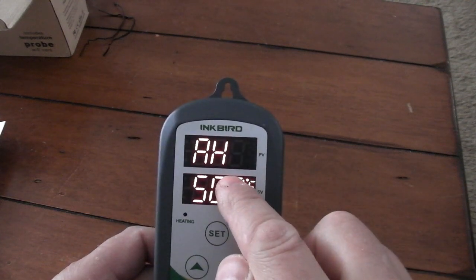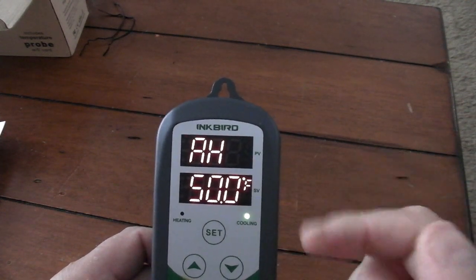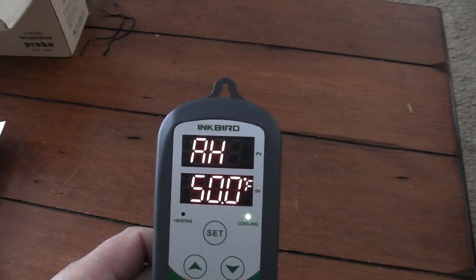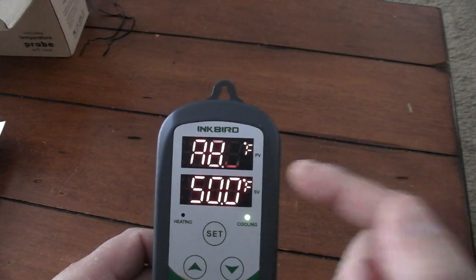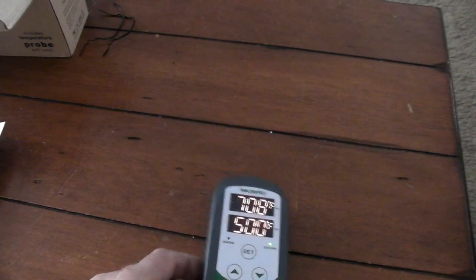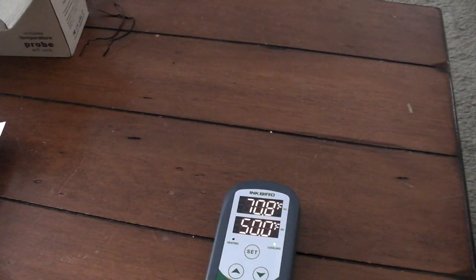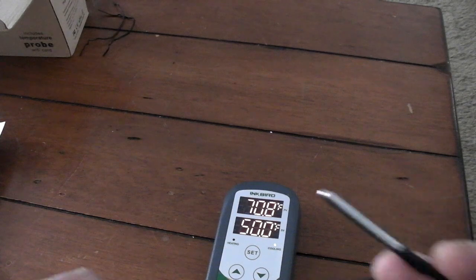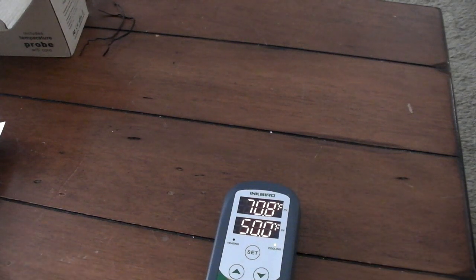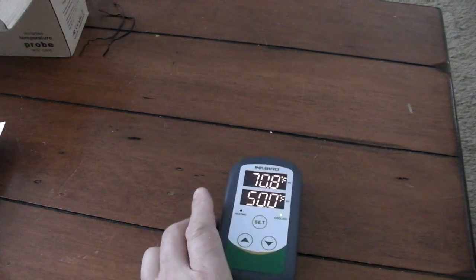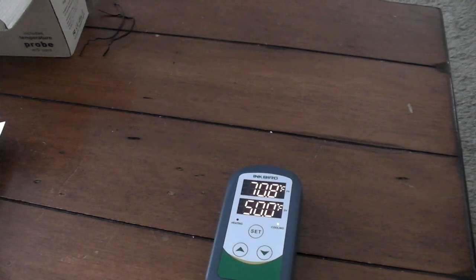Okay, it says alarm high, AH. It's cycling back and forth because it's actually too warm in here. The sensor is reading that it's over 70 degrees. So what I'm going to do is I'm going to unplug this. I'm going to see if it holds my settings.